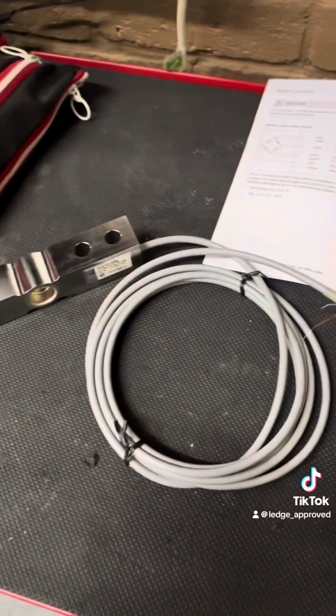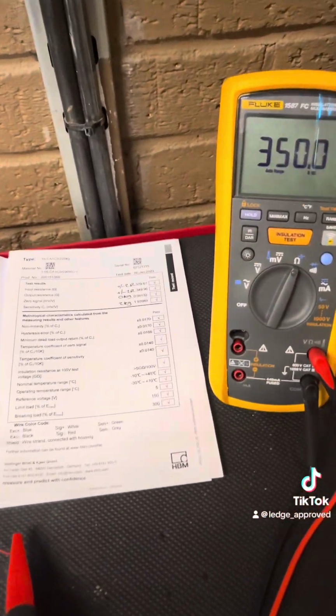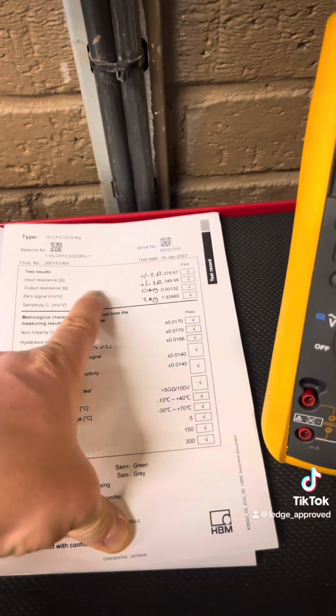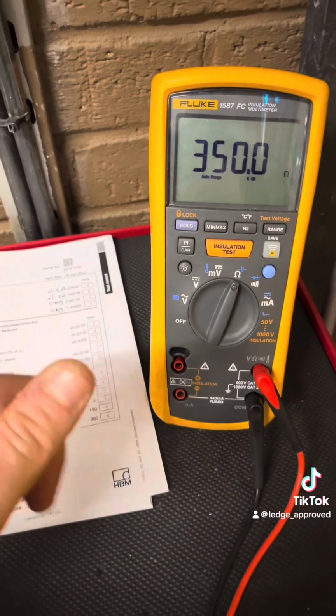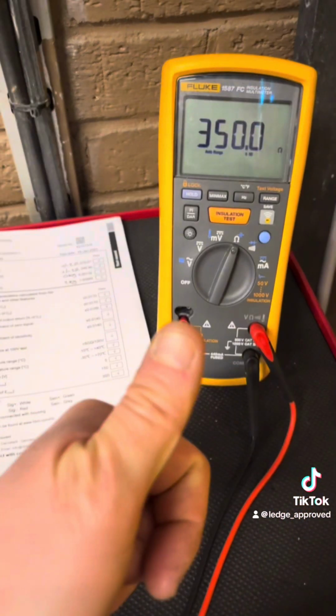And if this all comes back sweet, you know you've got a good load cell, and you've got to track your fault back to the PLC. But then if you've got any kind of throwing off, you know it's your load cell.